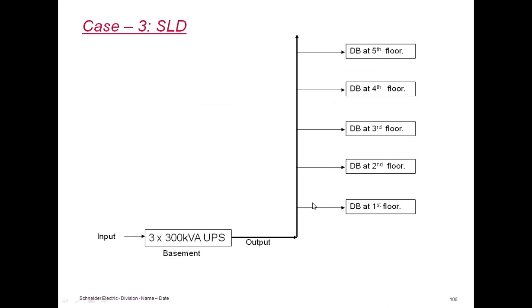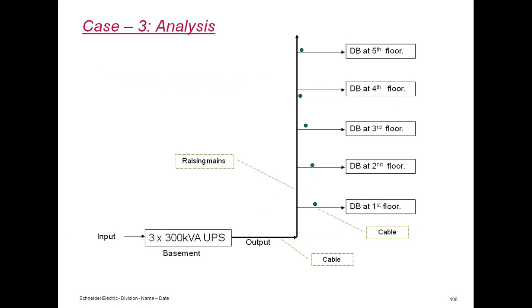So they observed that when they run 4 floors, nothing happens, everything is intact. When they run the 5th floor, there is an increase in ground current that triggers the leakage relay and trips the UPS output side. You know, the tripping of the UPS output is critical for the IT industry. If the UPS output trips, that means the entire IT building is off. There's huge revenue loss for the customer. So we analyzed, and this was the analysis we had.